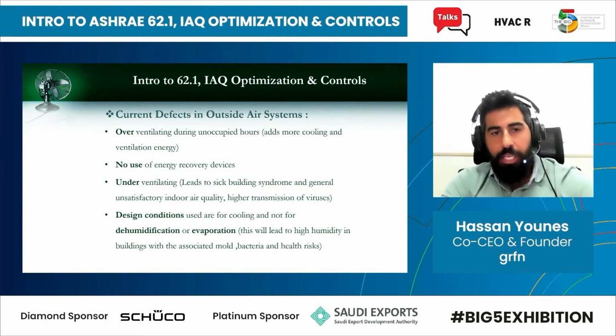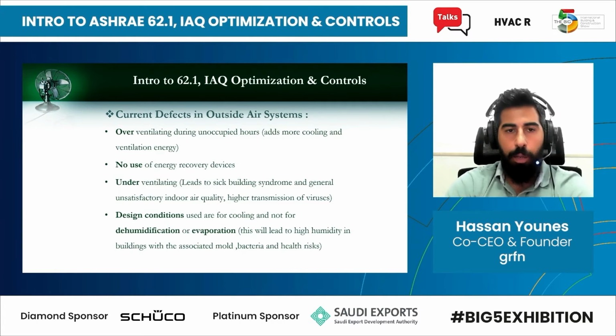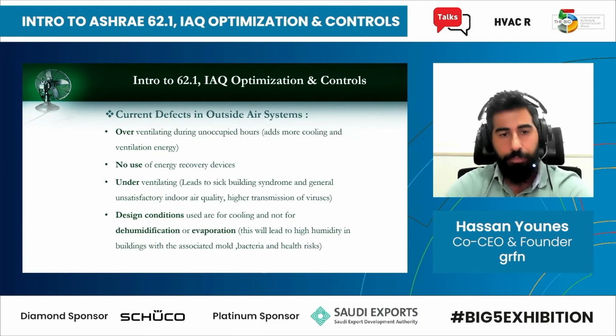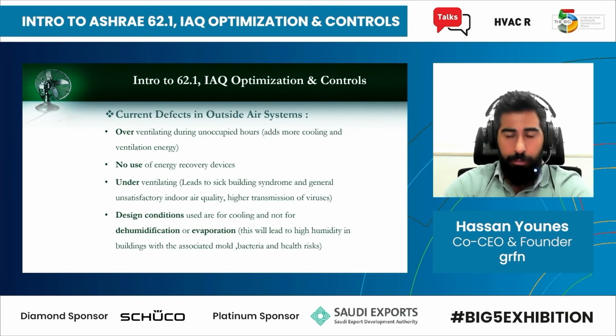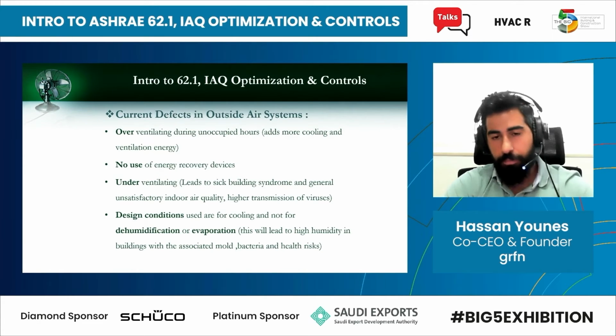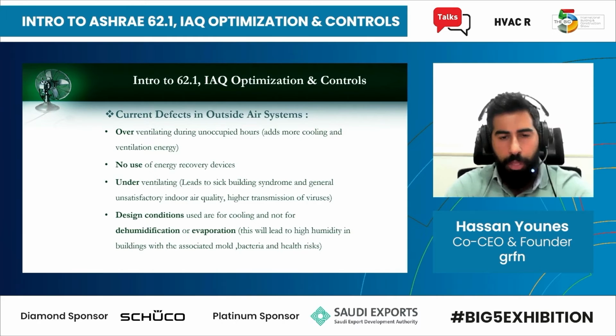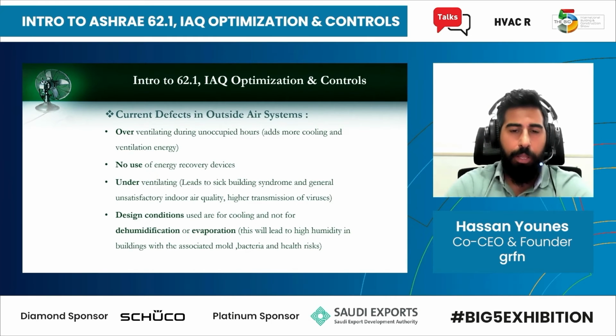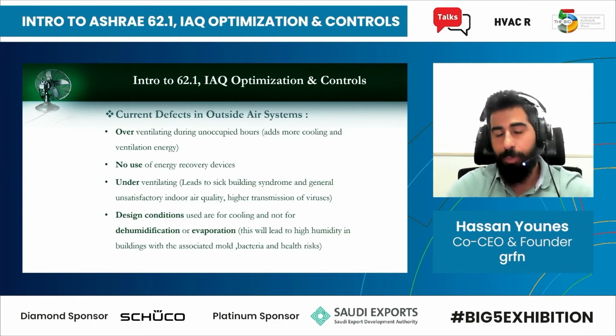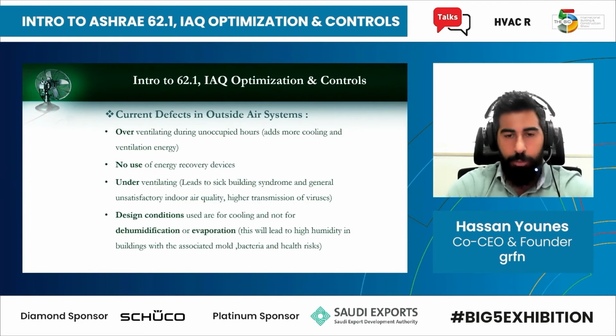Some of the current defects we see in the outdoor air systems: over-ventilating, and ventilating during unoccupied hours, which adds more cooling and ventilation energy. Basically you should just turn them off if there's no one there. No use of energy recovery devices. Under-ventilating, which leads to sick building syndrome and also higher transmission of viruses. Design conditions used are for cooling and not for dehumidification. And normally you want to use the dehumidification or evaporation design conditions for outside air handling units, especially in hot and humid climates.